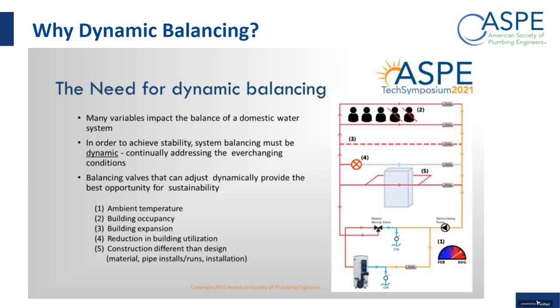So why do you need a dynamic balancing valve? Again, the manual balancing valves and the pressure independent are not dynamic. They're fixed. Once you set them, they're not changing. Well, there's a lot of reasons why you may need a dynamic balancing valve. And the brunt of it all is that if conditions change, the balancing is going to need to change.